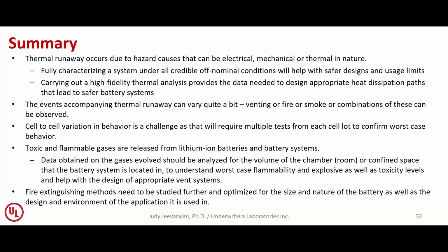The events accompanying thermal runaway can vary quite a bit. We saw venting, fire, or smoke—sometimes all three, sometimes just one or two. That's something you need to understand for your system. We also saw cell-to-cell variability within the same pack: one cell went into thermal runaway with fire, another had only smoke. These are things to keep in mind and design for the worst case.